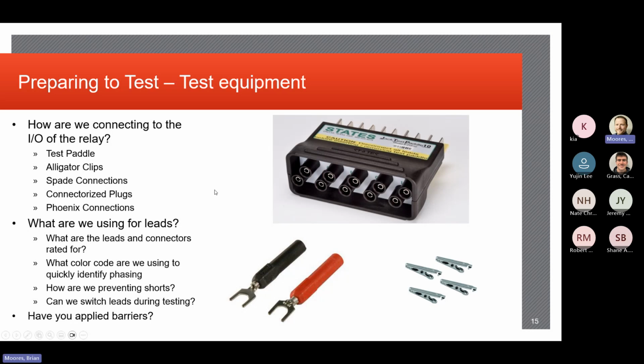All right. And then, yeah, barriers. We talked about some HPI tools, physical tools. You can put barriers, you can put tape, electrical tape, dielectric, vinyl, something to help with avoiding touching exposed parts, energized exposed parts, or just physical tags or barrier tape or something so that you can create your zone. Like, don't open this test switch, only open this one. Don't operate this switch, only operate this switch, work in this relay, that sort of stuff.